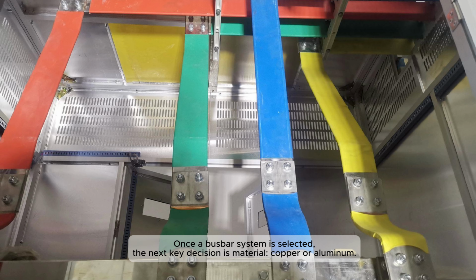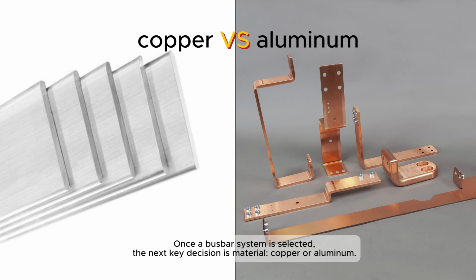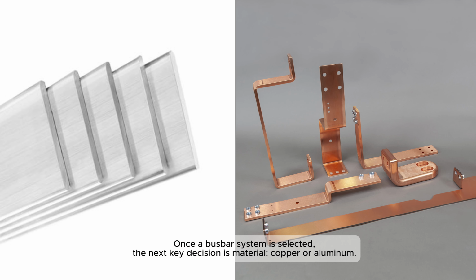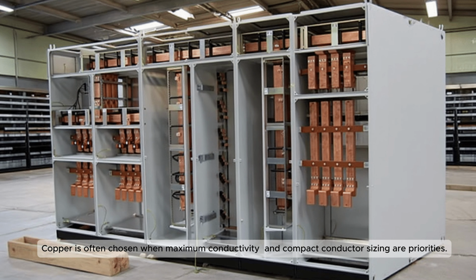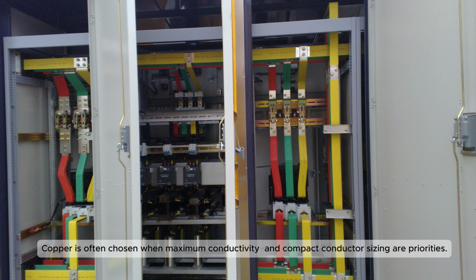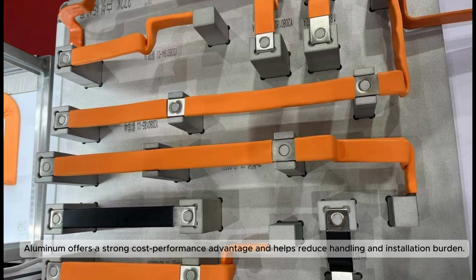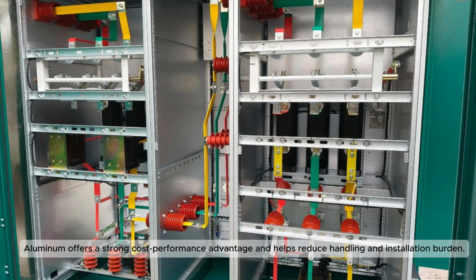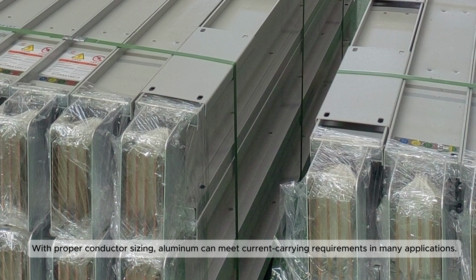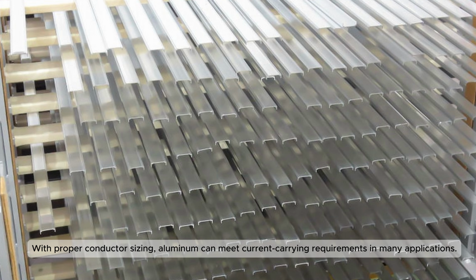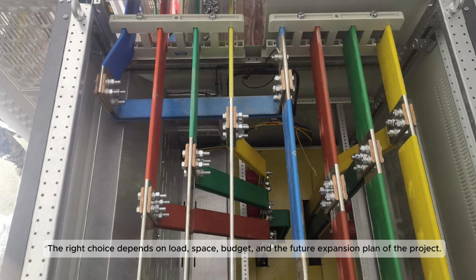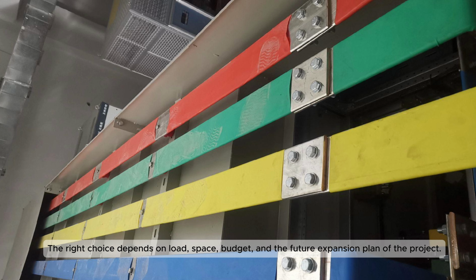Once a busbar system is selected, the next key decision is material, copper or aluminum. Copper is often chosen when maximum conductivity and compact conductor sizing are priorities. Aluminum offers a strong cost-performance advantage and helps reduce handling and installation burden. With proper conductor sizing, aluminum can meet current carrying requirements in many applications. The right choice depends on load, space, budget, and the future expansion plan of the project.